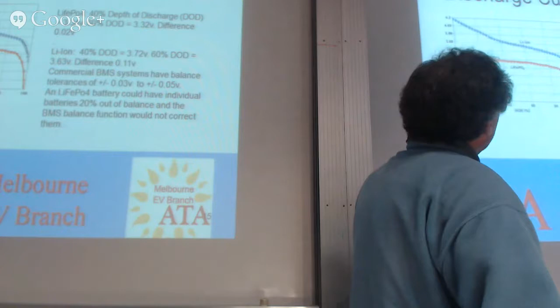Go on to the next slide. So, some of the conclusions from that. With LiFePO4 batteries, the BMS must be of a very high standard and has a lot more stress on it than with the other lithium-ion chemistries. Lithium cobalt, NMC, the voltage ranges are wider, and the BMS has a lot more range to work in. Therefore, there are more BMS-related failures in LiFePO4 batteries than in the other chemistries, due to the batteries drifting out of balance and the BMS not being able to correct it.